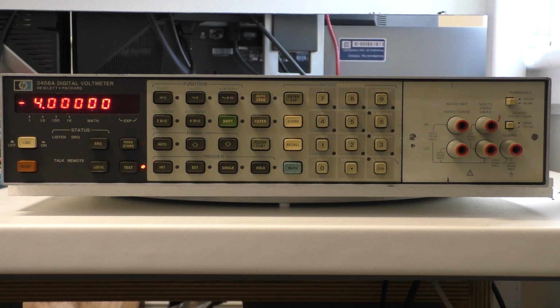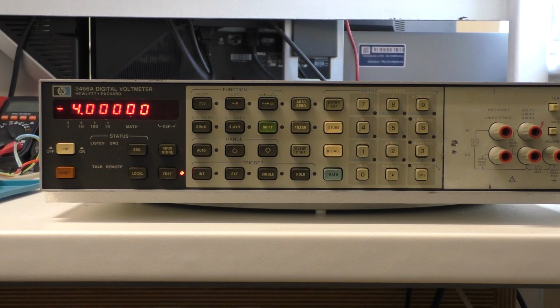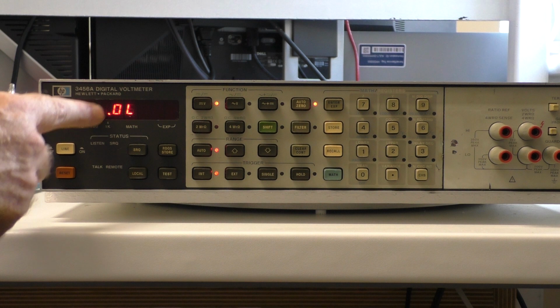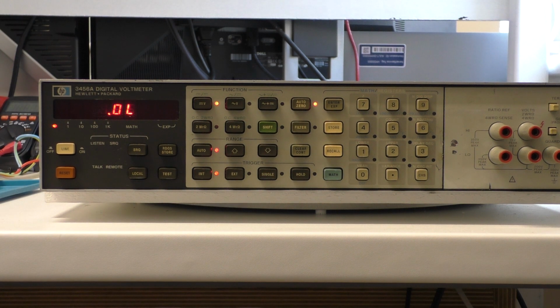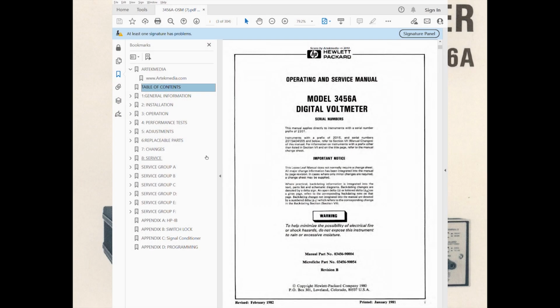After a few minutes our meter starts to present the failure code 4. When we take the unit out of test mode by hitting the test button, we see the overload displaying on the meter. Clearly this meter has an issue. Let's take a look at the service manual to see how to resolve this problem.